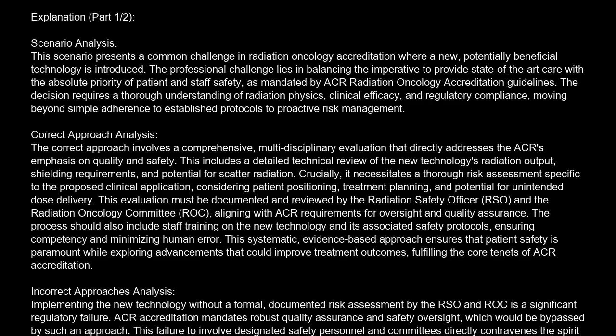The correct answer is B. Conduct a comprehensive, documented radiation safety evaluation by the Radiation Safety Officer and Radiation Oncology Committee, including independent verification of the accessory's performance and potential risks prior to any clinical use.